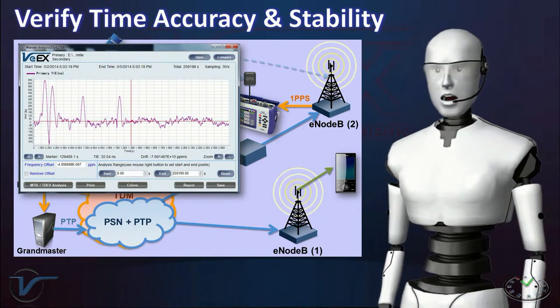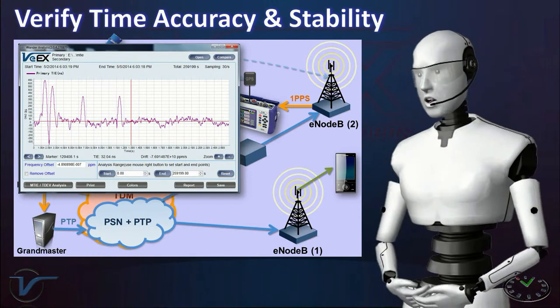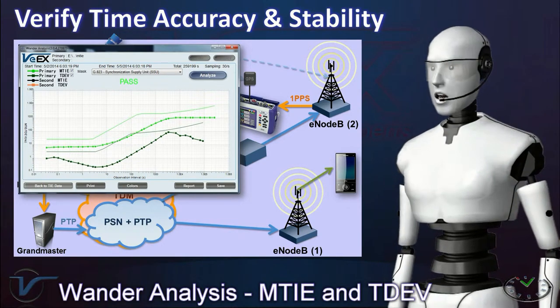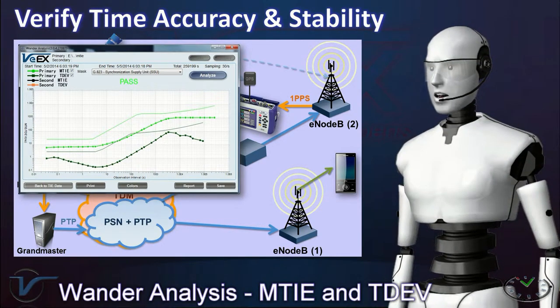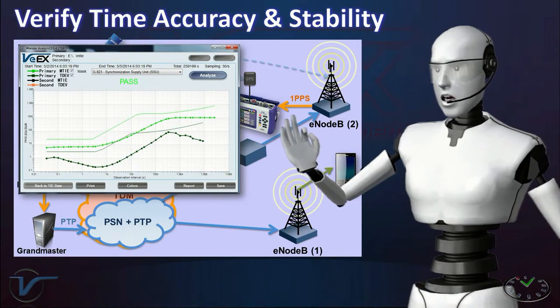The same test can also monitor the timing signal over time to see how much it wanders and assess its stability. You can perform wander analysis on the recorded phase behavior. At the end, the one PPS timing signal under test must be accurate and stable.